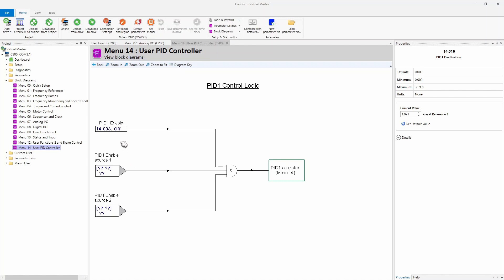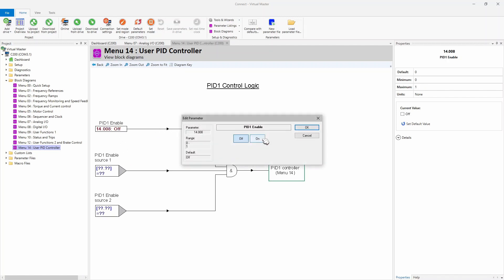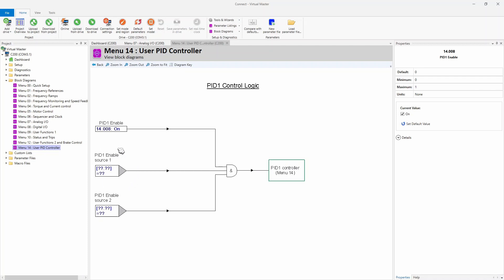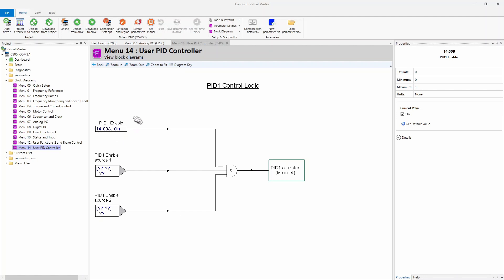I did not talk about this previously, but you should have this on. You may not want it on all of the time. For example, you might want to tie a digital input to this enable or a piece of code. For example, if the drive is disabled or tripped, there's no reason having your PID running. You could also enable and disable this, tying it to drive healthy and active so that it automatically disables itself. Now you'll notice that there's three of them here. If you don't map these two, it just assumes that it's true on this end block. And so this is the only one you have to actually control.